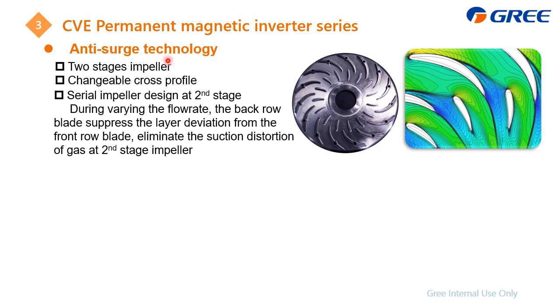Next is the anti-surge technology for this CVE. As you know, the compressor RPM can be changed, which means the discharge pressure can also change, so anti-surge is not that easy compared with the CE on-off compressor. The first three, which are from the mechanical design, ensure the discharge pressure is as high as possible: the two-stage impeller, the changeable cross profile, and the series impeller design at the second stage impeller. It is just like a relay race: we need to ensure the flow is smooth to lower the resistance, which can raise the discharge pressure.